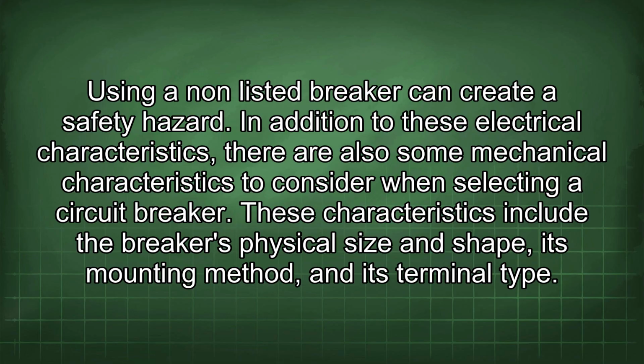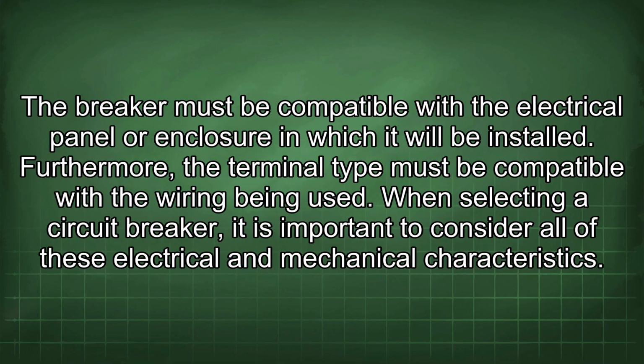In addition to these electrical characteristics, there are also some mechanical characteristics to consider when selecting a circuit breaker. These characteristics include the breaker's physical size and shape, its mounting method, and its terminal type. The breaker must be compatible with the electrical panel or enclosure in which it will be installed. Furthermore, the terminal type must be compatible with the wiring being used.